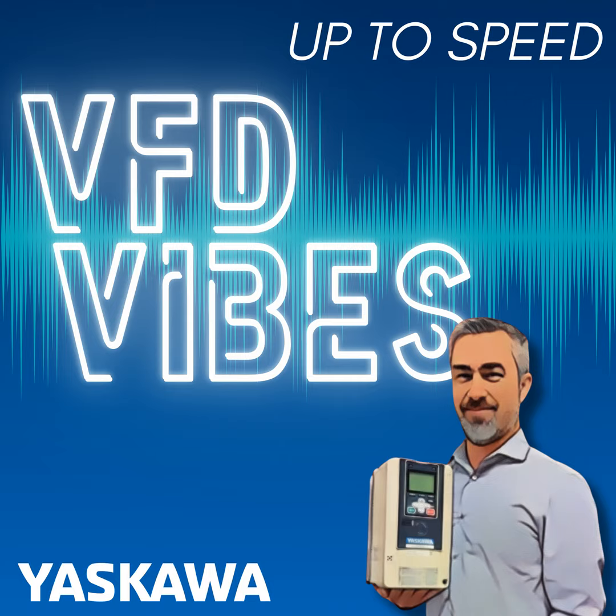Filter maintenance is especially important on UL Type 12 enclosures that rely on filtered airflow. The filter is there to keep the air clean in the panel, but to do so, it removes particles out of that air, and as those build up on the filter, the ability for air to flow freely through the filter gets reduced. You need to make sure you're properly cleaning or replacing those filters on scheduled maintenance. And if the filter has even a small tear, it's time to replace it. Don't patch it, don't put duct tape on it, and hope to get another year out of it.